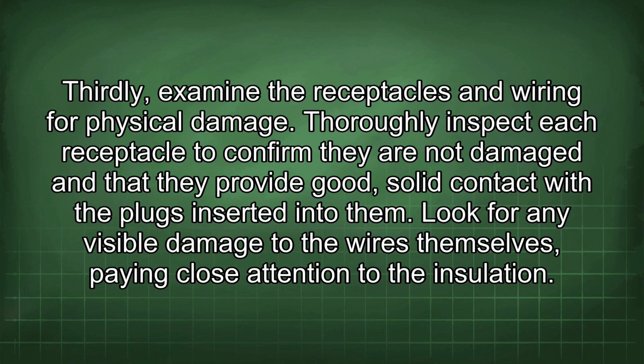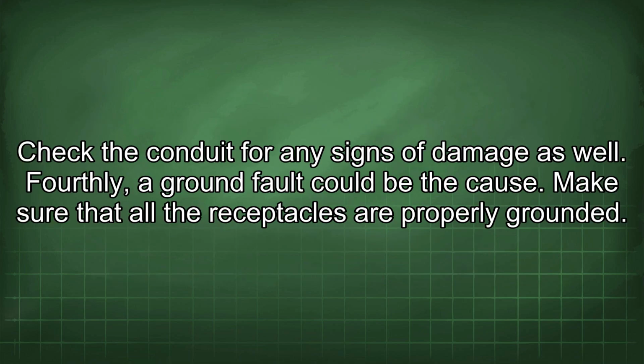Thirdly, examine the receptacles and wiring for physical damage. Thoroughly inspect each receptacle to confirm they are not damaged and that they provide good, solid contact with the plugs inserted into them. Look for any visible damage to the wires themselves, paying close attention to the insulation. Check the conduit for any signs of damage as well.